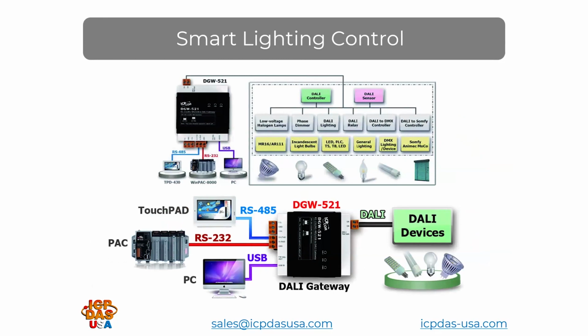DGW-521 is a communication gateway between the Modbus RTU DCON and the DALI Digital Addressable Lighting Interface protocols, and allows a host PC, PAC, or touchpad to access DALI devices by providing 3 interfaces that enable conversions from RS-232, RS-485, USB to DALI. The module provides a built-in DALI power supply that can be enabled or disabled via a switch. DALI is an international standard for lighting control interfaces and is suitable for DALI lighting system covering small areas. The maximum length of the DALI signal cable cannot exceed 300 meters.